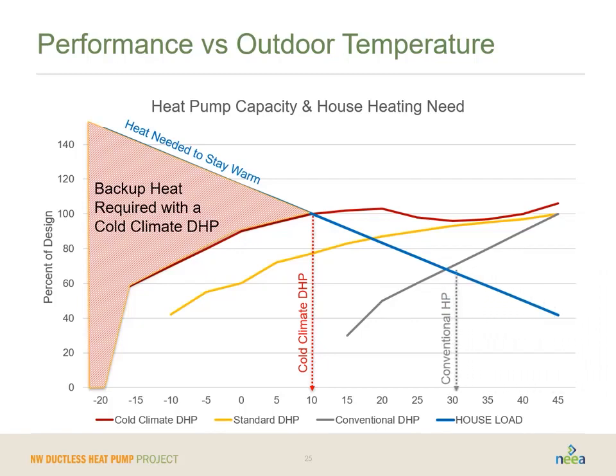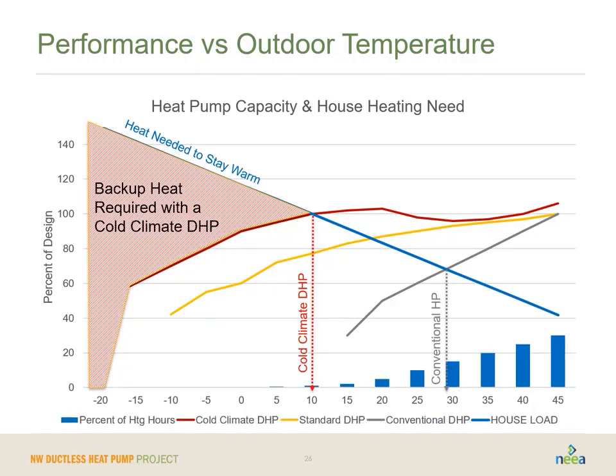This is just showing that comparison still between that cold climate and the air source heat pump. And while, yes, it is true that the majority of the time is spent where an air source heat pump would do the job, there's still a fair amount at the 15 degree, 20 degree, and 25 degree temperature that would need to be addressed by backup heat if you have a standard air source heat pump. Whereas with the cold climate ductless heat pump, you're only really ever going to need that backup heat for a very, very small percentage of the time.